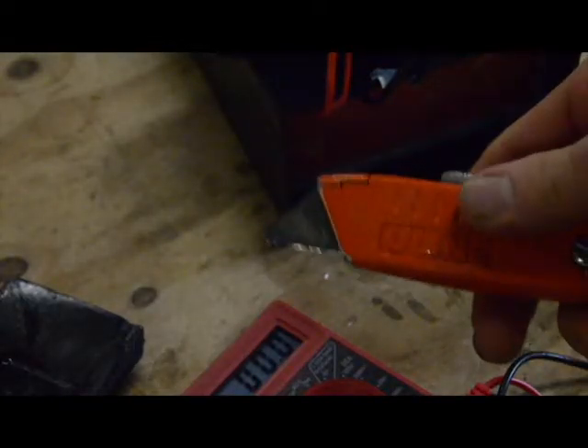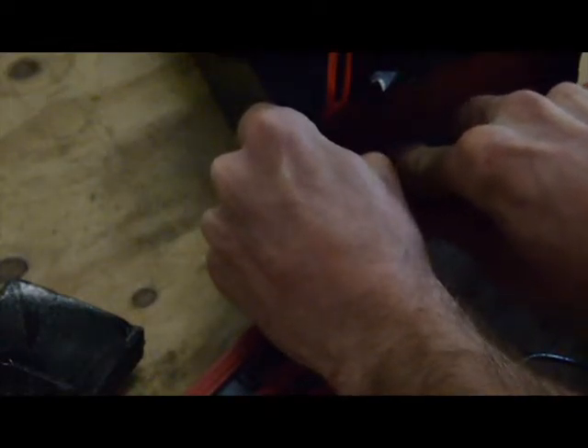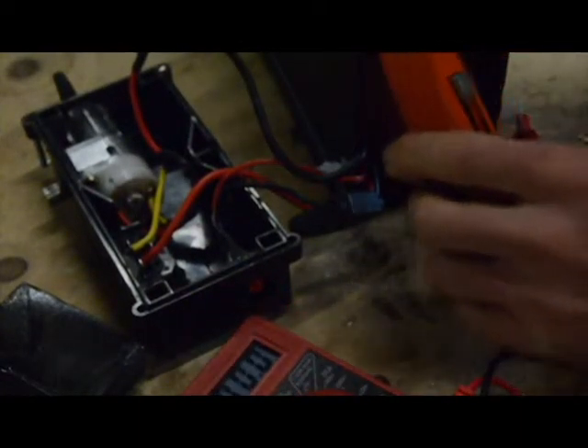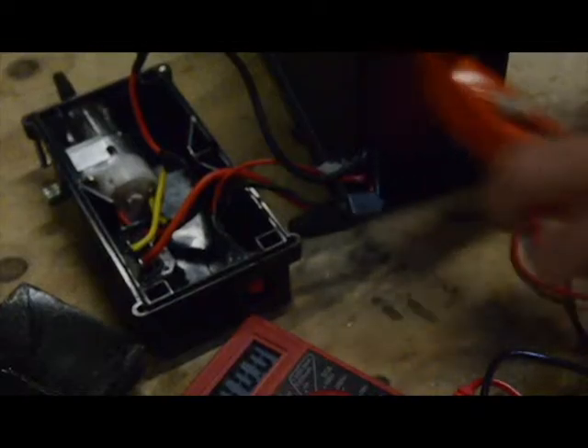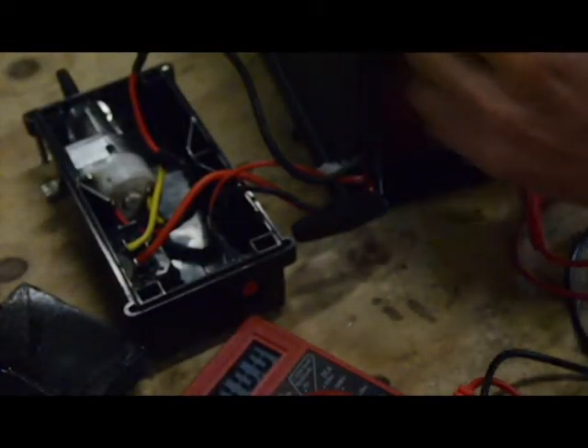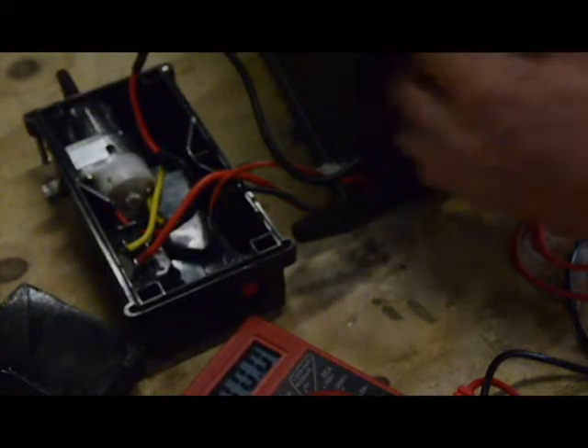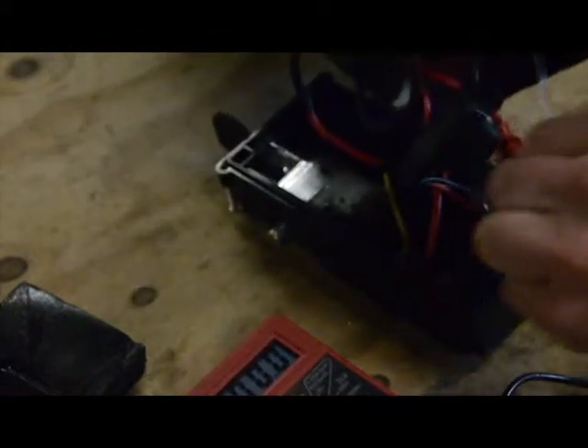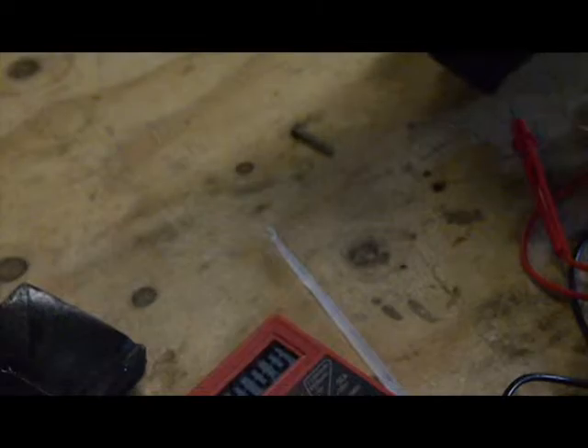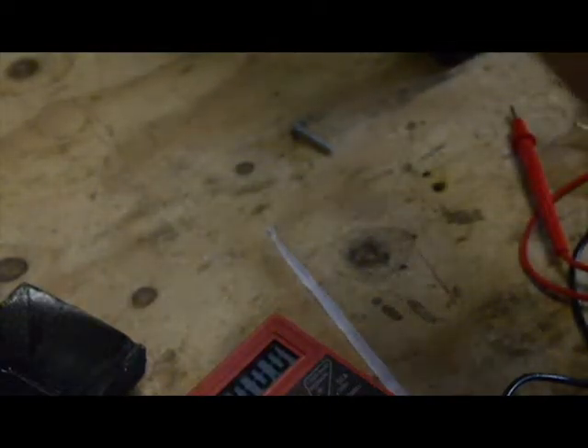Do that with a sharp knife, and we need to cut this hot glue back, and be careful when we're doing this, because there is no way to shut this battery off except at the switch. So you need to be mindful of where your knife is going. You don't want to be cutting any wires right now. You just want to be removing the glue. Also, don't cut too deep, because underneath here is our BMS circuit board, and we don't want to damage that. So just enough to get this glue peeled back.